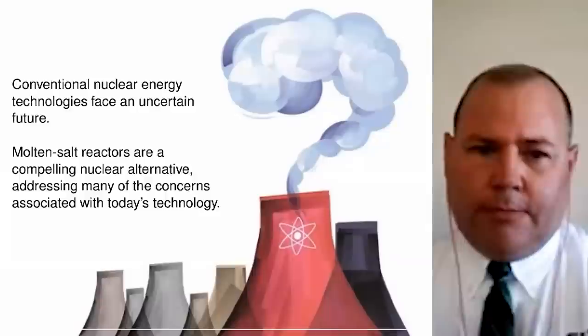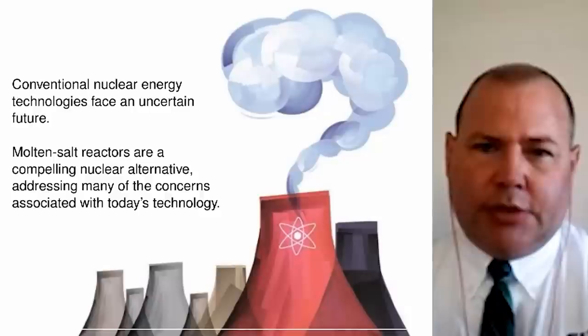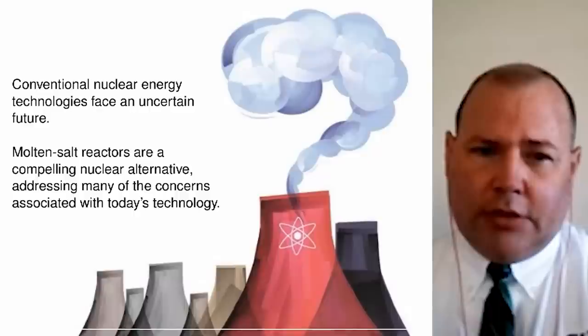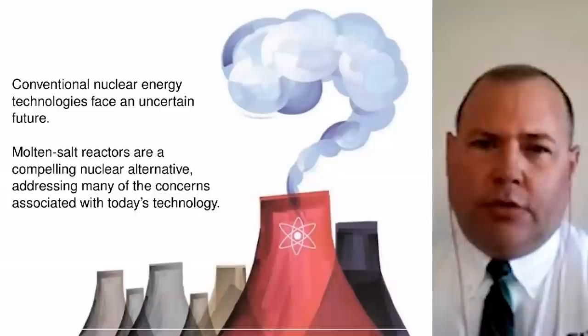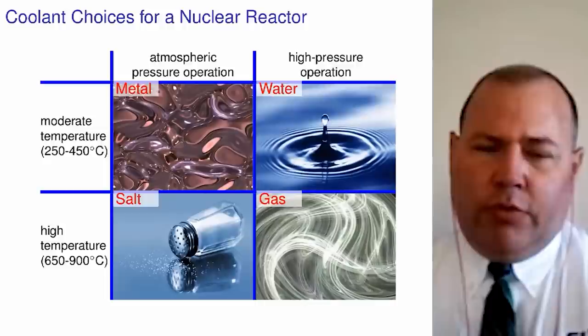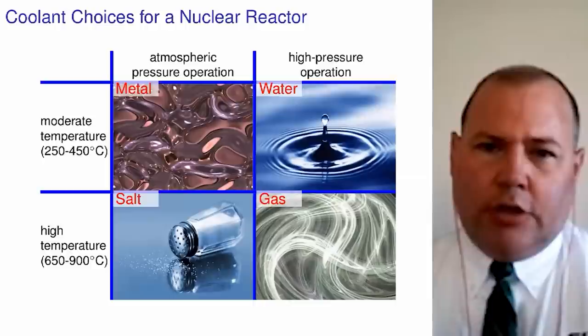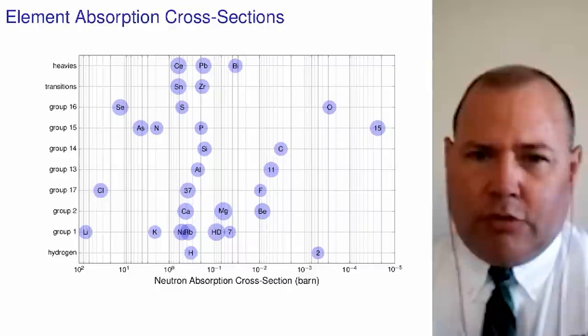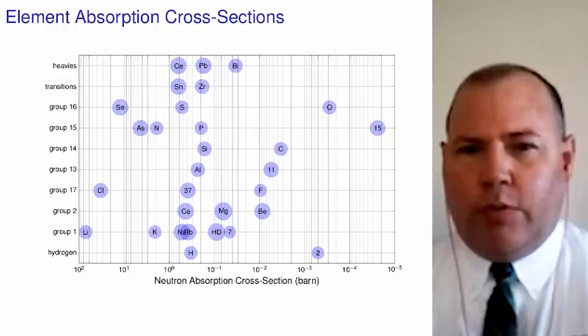We're compelled to look at alternatives to today's power generation because of uncertainties both in terrestrial production, carbon emissions, as well as existing nuclear technologies. We believe strongly that molten salt reactors are a very compelling alternative. The value proposition for molten salt is that this is the only coolant choice that can operate at really quite high temperatures as well as at low pressures. But you have to figure out what you're going to make the salts out of, and if you look at materials with low absorption cross sections, the field narrows pretty quickly when you're trying to do something neutronically efficient.